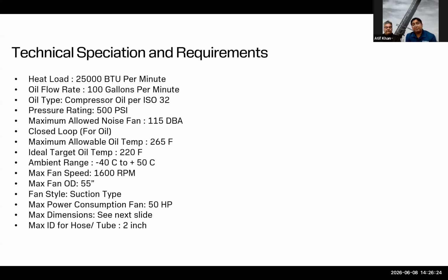The maximum temperature that we would like our oil to reach is 265 Fahrenheit. Our machine is highly self-regulating. The moment it sees temperatures going beyond a specific threshold, it shuts itself down. So this 265 is going to be that temperature. We are continuously monitoring the temperature, and the moment the machine sees it, it shuts down so that further damage doesn't happen. And of course, there is the ideal temperature. The maximum is 265 F, but we would always like it to be in the range of 220 F.